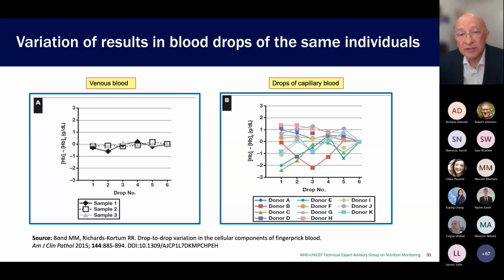And this is for completing my talk. This is a study with 6 individuals, and 6 individuals were sufficient to show what is in this picture. It's using HemoCue. In the left panel are 5 different estimations of hemoglobin concentration using the HemoCue with venous blood. You can see the precision of the machine, with very good and reproducible results.